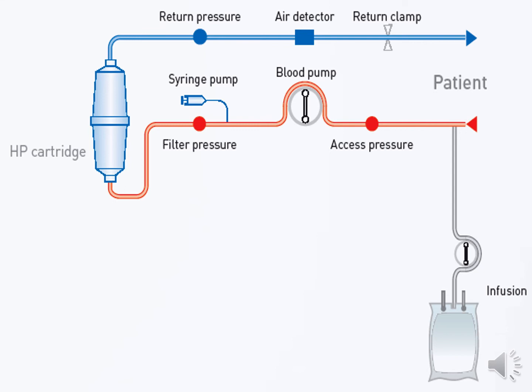You still have a similar setup, in the sense that you've got an access line which goes to the cartridge, which is not a hemofilter, it's a hemoperfusion cartridge. And then you have the return line which goes back to the patient, where contaminants are adhered to or adsorbed to the filter. And at the same time you've got the infusion, and the infusion essentially is fresh plasma.